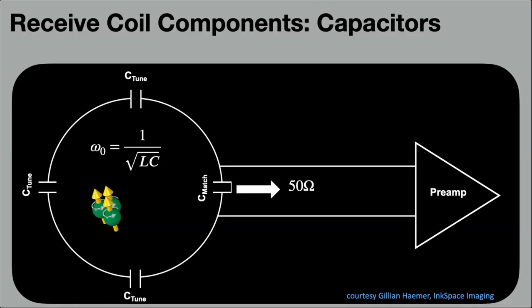And then you also want the impedance of the coil to match the transmission line, which is usually 50 ohms, although some systems are 75 ohms, so you have to look at what you're matching to. So you add these capacitors, and now this is resonant, and it's very sensitive to the signal at the Larmor frequency coming from the spins.